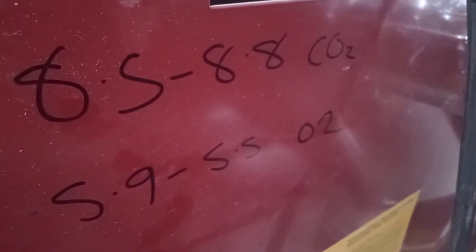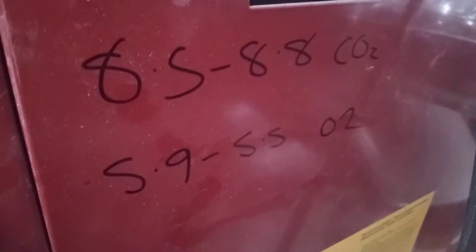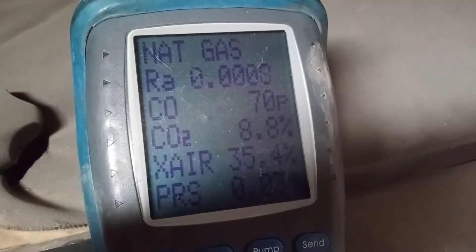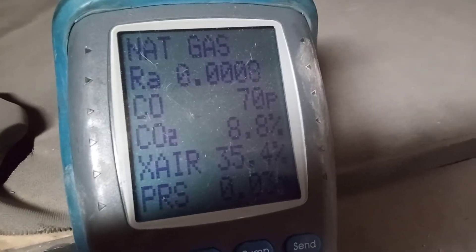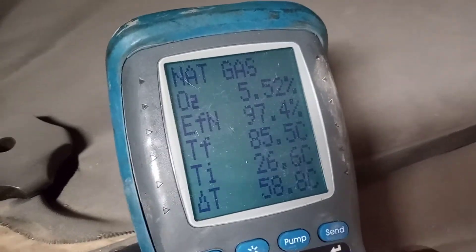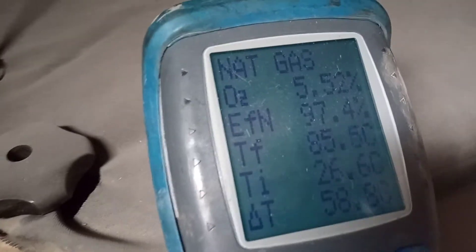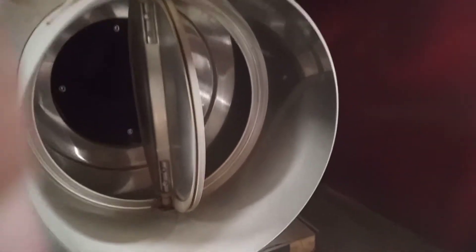I've written on the back of the boiler to remind me. Currently we're in high fire and we have 8.8 CO2. Our high fire and low fire readings are good. Here's our air inlet.